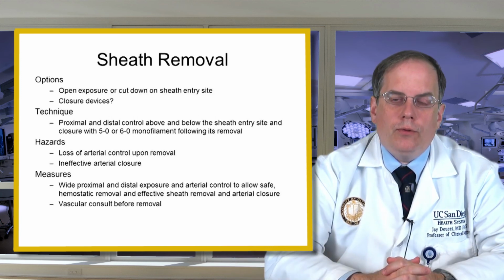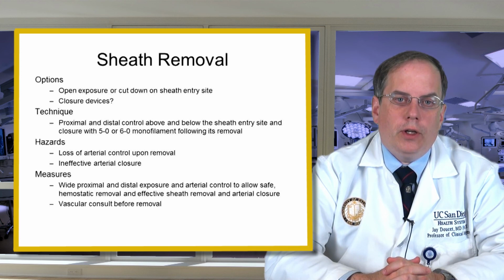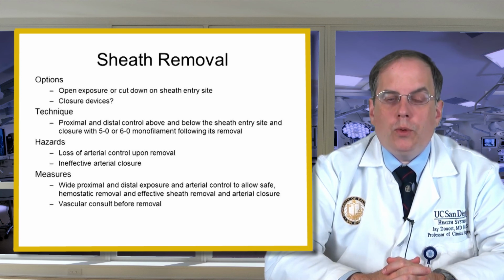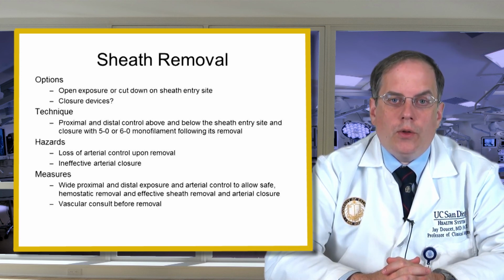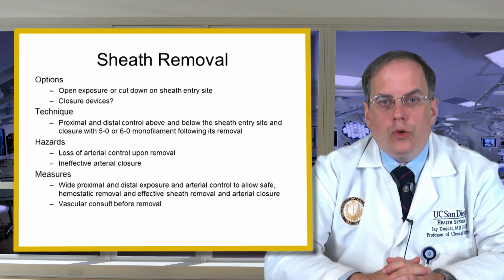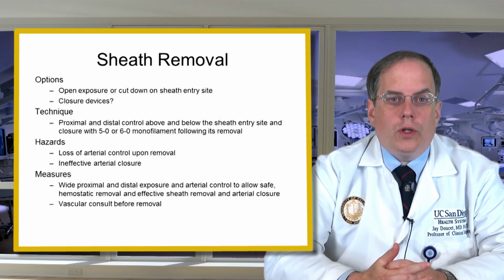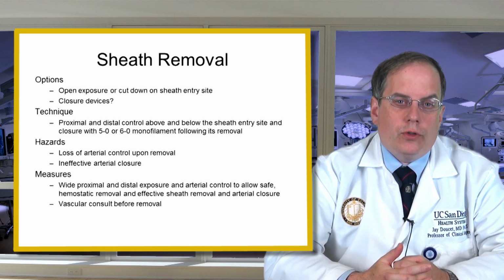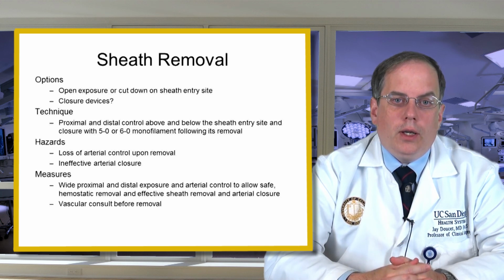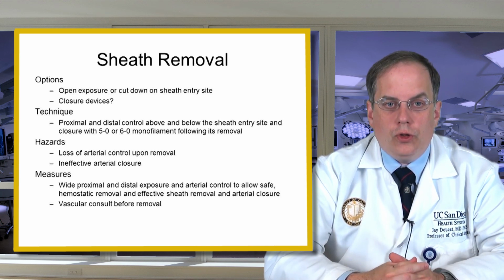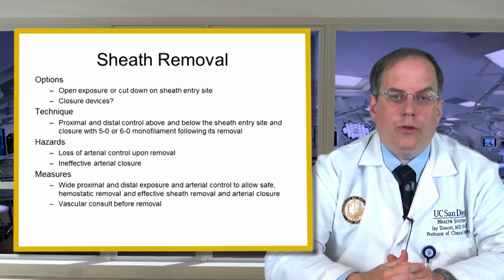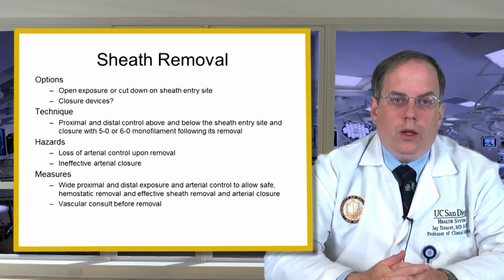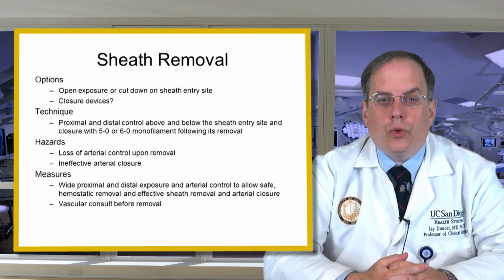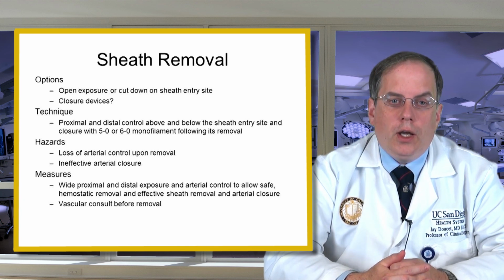Sheath removal involves closing the arteriotomy site. This probably will require open exposure or cut down on the sheath entry site and closure with suture. Currently, we don't have closure devices for such a large device. However, it is possible that with smaller sheaths in the future, with smaller devices, a closure device could be used. The technique involves proximal and distal control above and below the sheath entry site and closure with something like a 5 or 6/0 monofilament suture after removal of the sheath.